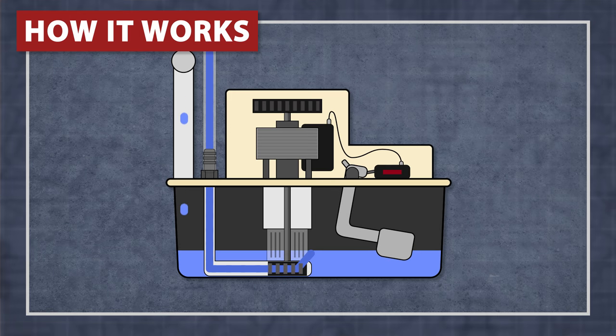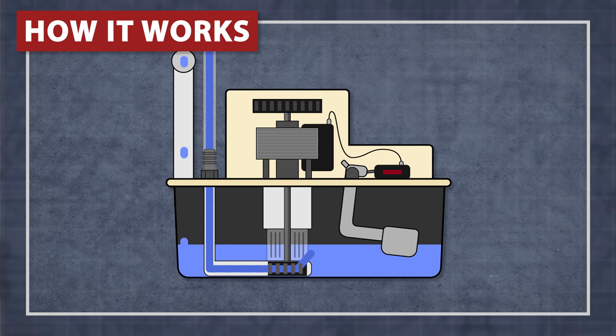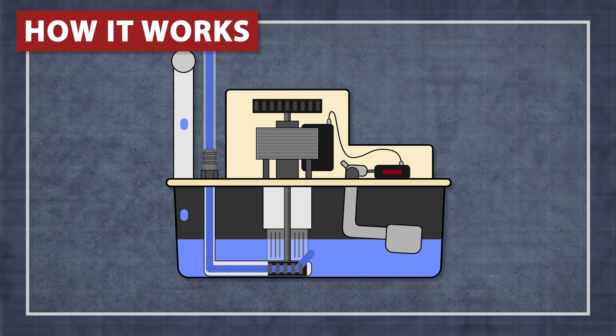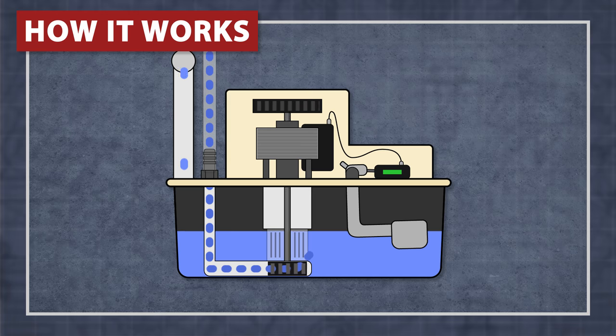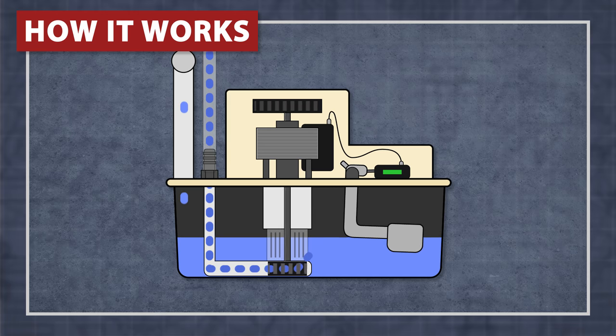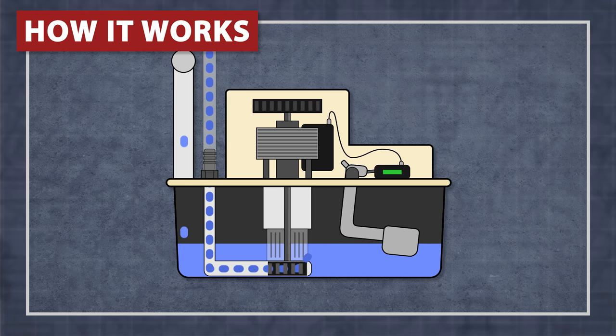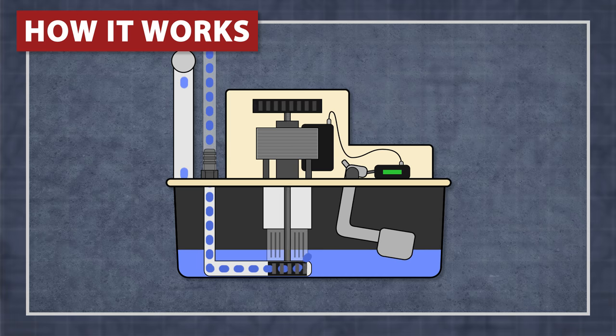As water flows into the condensate pump basin, the water level rises and triggers the float switch. The motor then pumps the water up through the discharge tube. When the water level drops, the float switch disengages and shuts off the pump.